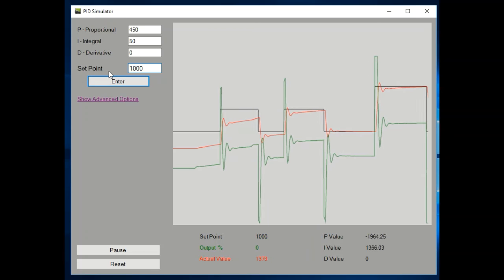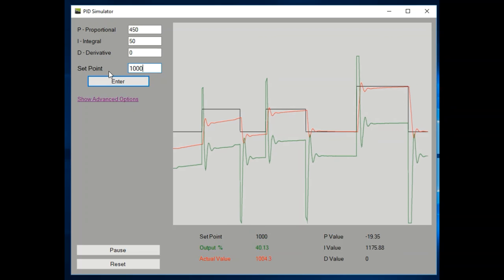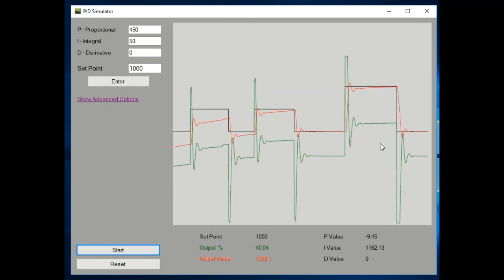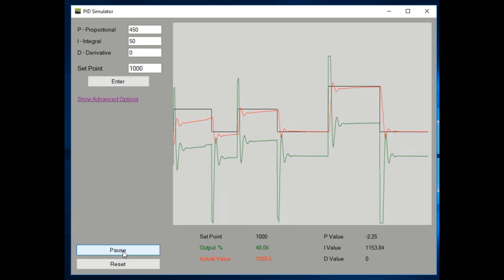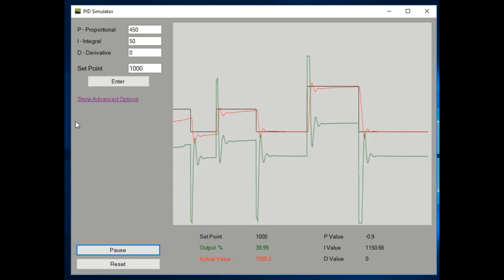Increasing it again and trying again. There's no set formula for a PID control loop other than changing the gain factors on the P, the I, and the D, and watching the reaction. The reaction time is great with the proportional, with the output dropping right down to bring the value down. Slight oscillation, but very stable within one cycle. The integral brings us to the set point, but we have an overshoot or undershoot here. In some applications that might be fine — fast acting, stable, reaches the set point. But in finicky applications, you need to smooth that out. That's where the derivative comes into play.